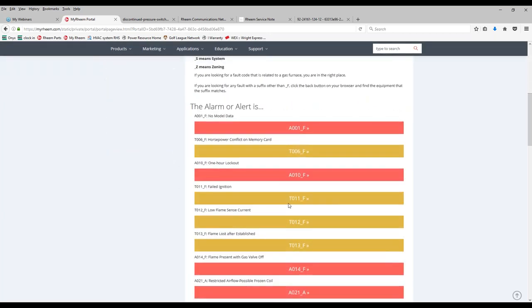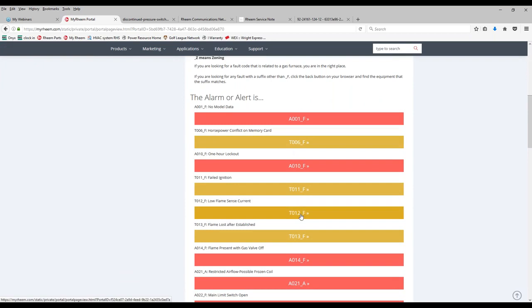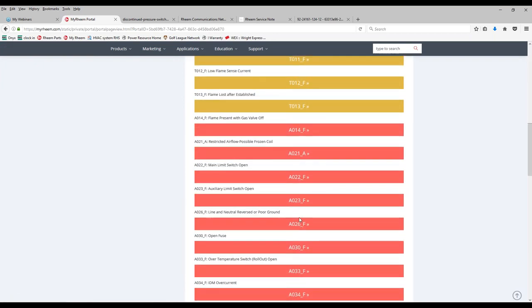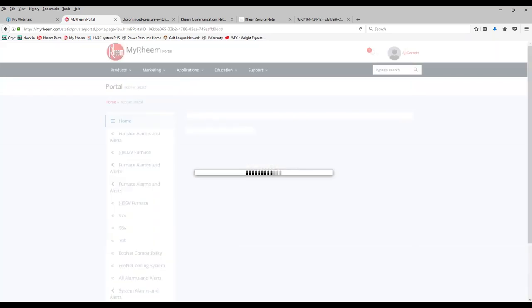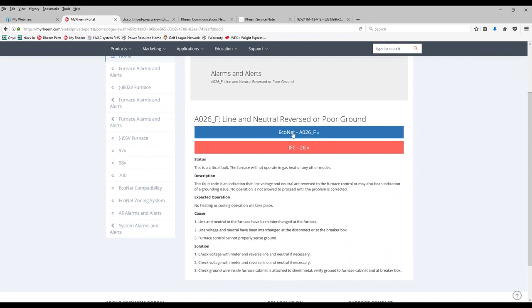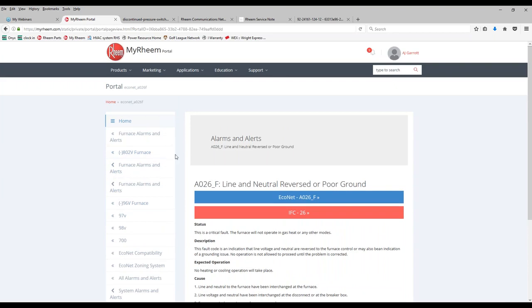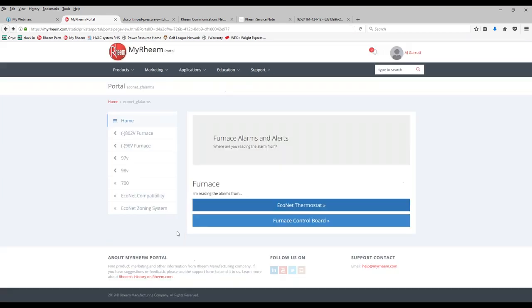and it'll come down through and give you all your error codes that you will receive from that 96 variable speed. So say we get down to an A026_F. F will stand for furnace. We're going to click on that. Here it'll tell you what you see at the Econet, what you see at your IFC on the actual gas furnace control board, and how to troubleshoot it or what to look for. This is some really good information that I suggest you get to all your service techs. This is information we're looking up all the time, helping everybody out.